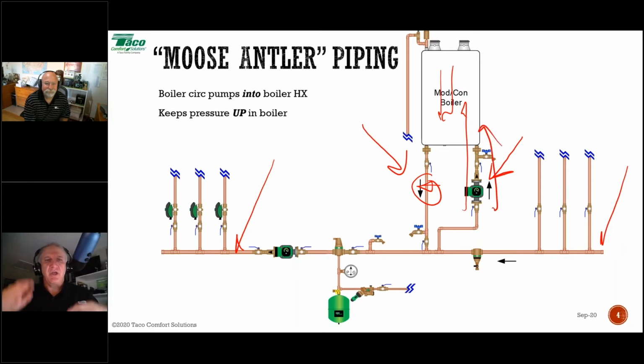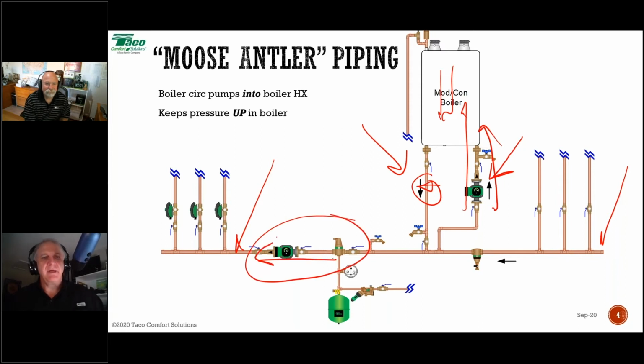That has nothing to do with quote unquote pumping away. We're not pumping away from the boiler. This right here is pumping away, where we're pumping away from the point of no pressure change, that position where the expansion tank connects to the air separator and connects to the system. That we're pumping away. This has absolutely nothing to do with quote unquote pumping away. All right. So I hope that one makes sense. That's your basic piping arrangement.